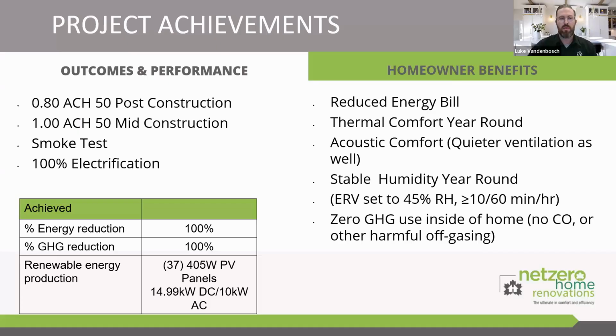One thing I wanted to point out is this home had a significantly oversized heating system for the 800 square feet it previously was. When the system would kick on, you'd get a loud oil can bang, then after a 10 to 15 minute cycle the whole system would turn off, and you'd get the reverse bang of the duct system depressurizing, followed by deafening silence from that background noise being removed.